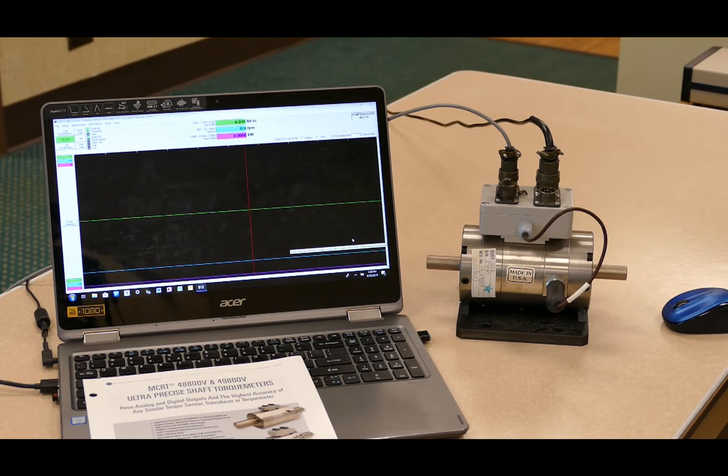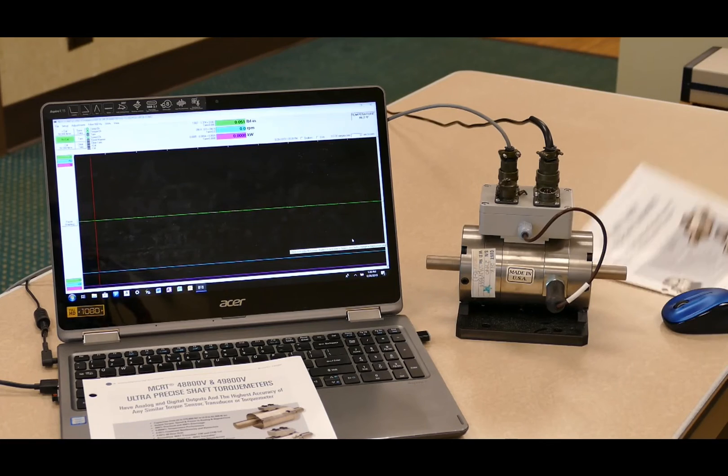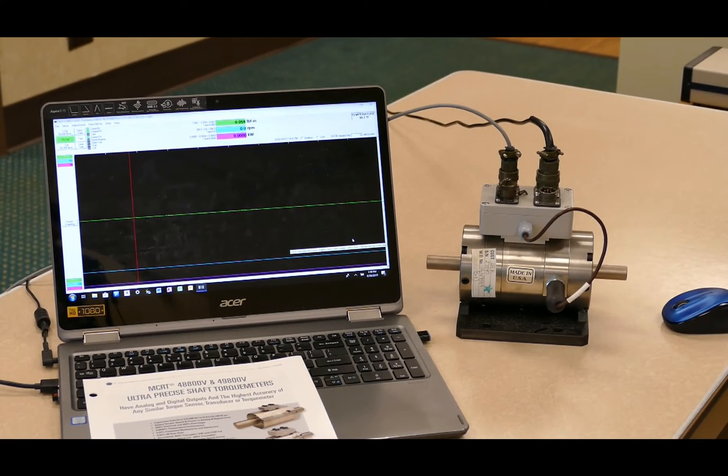All units feature significant overrange on the electrical output signal. That means we don't clip at full scale. We allow the electrical output to extend beyond its full scale, so instead of stopping at 10 volts, the electrical output will extend up to 15 volts. The advantage of this overrange is that it will not clip the peaks and it will not affect the accuracy of the average display torque.